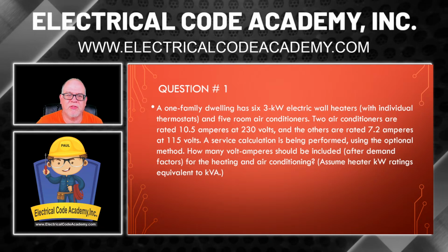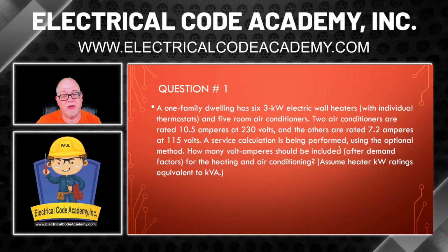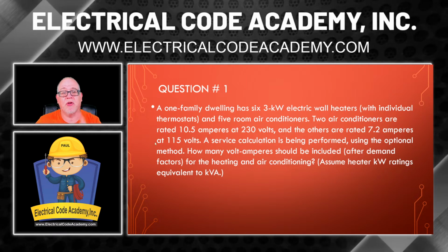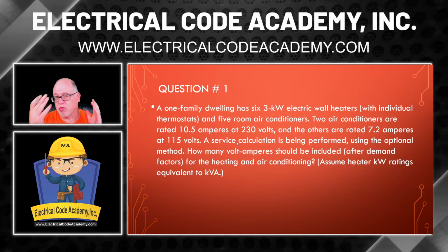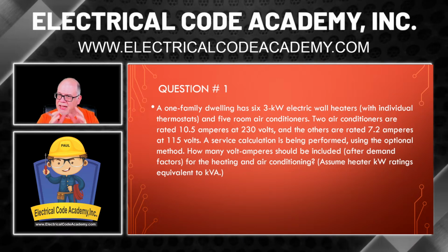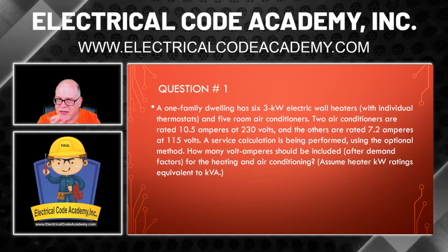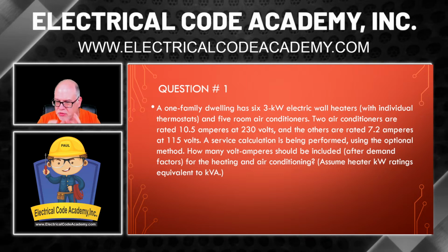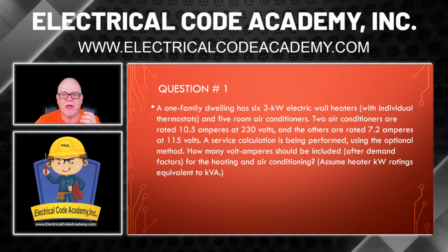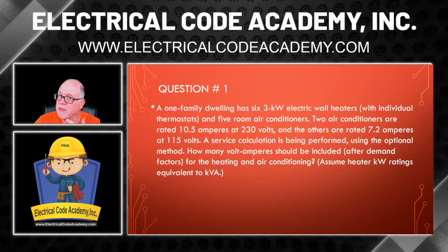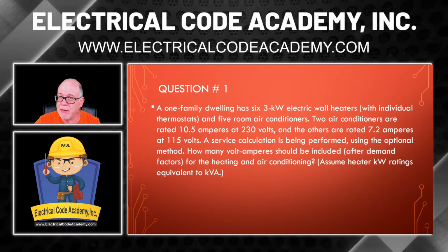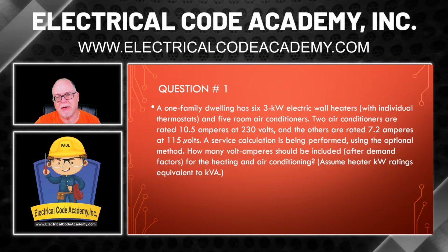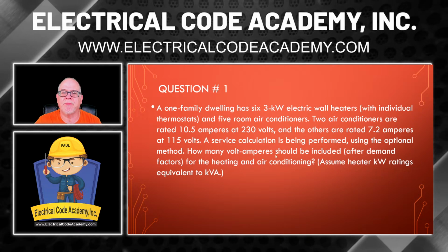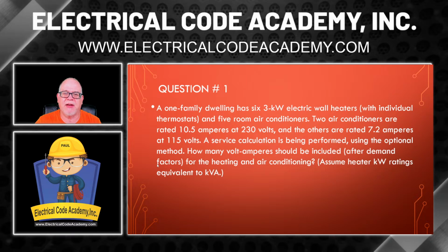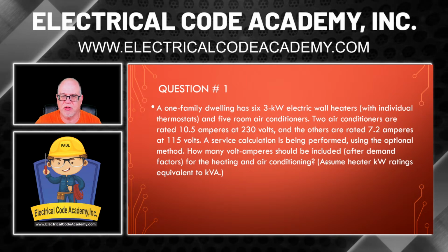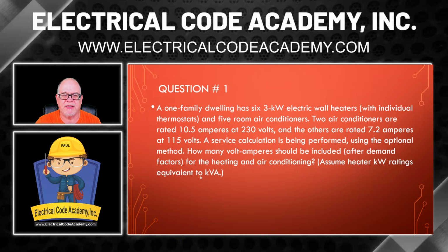All right, now it goes on to say, a service calculation is being performed using the optional method. So they'll be using the optional method to do their overall service calc. But it seems like we're only being asked to do the AC and the heat and compare the two. It is reminding you that they're using the optional method, so that puts you in the optional area, which would be part 4 of 220, right? It says, now, how many volt amperes should be included after demand factors for the heating and air conditioning? Assume heater kW ratings are equivalent to kVA.